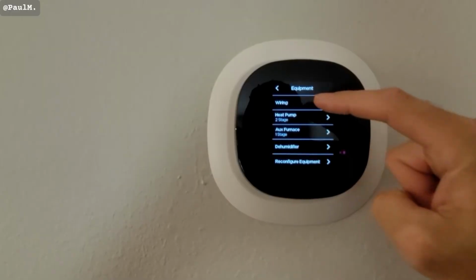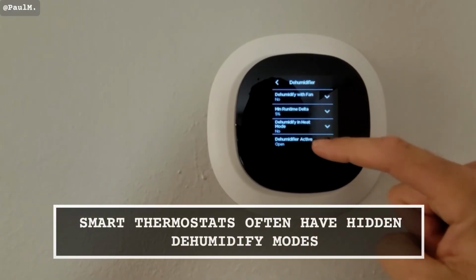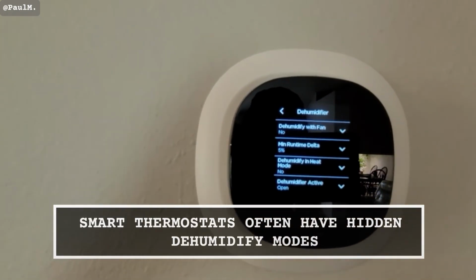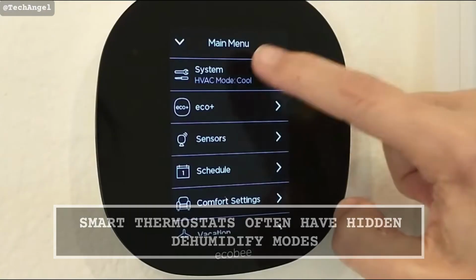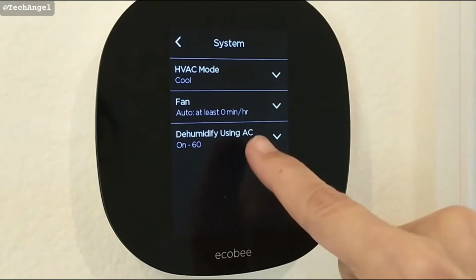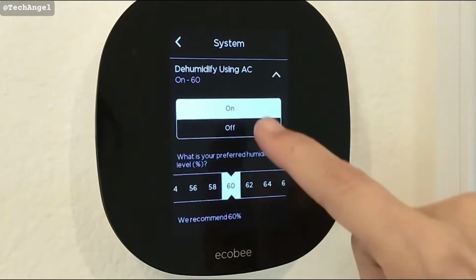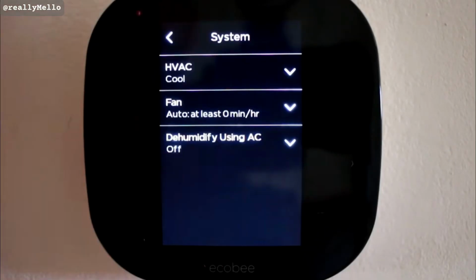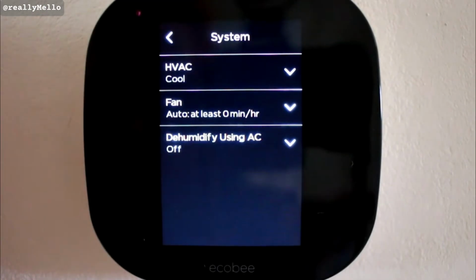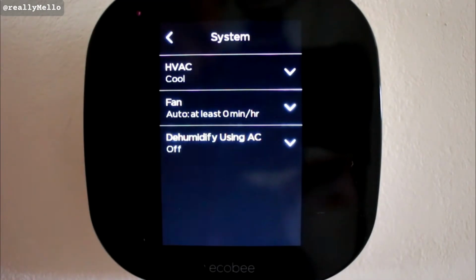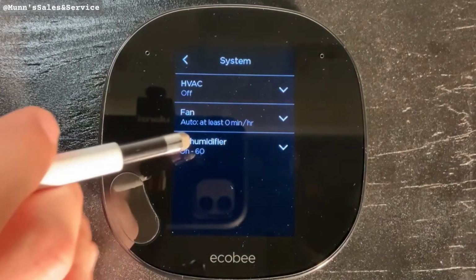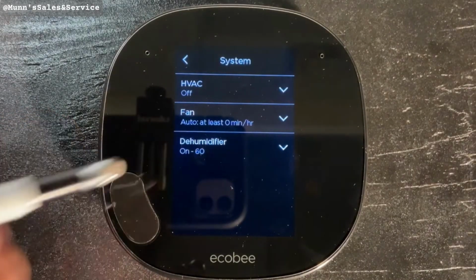Number 23. Most smart thermostats from Ecobee, Nest and Honeywell have a hidden dehumidify mode that overcools by 1 to 2 degrees Fahrenheit when indoor humidity rises above your set point. Most installers leave it disabled because they don't know it's there. Enable it through the installer menu, and your humid summer days get significantly more comfortable for 0 extra equipment cost.